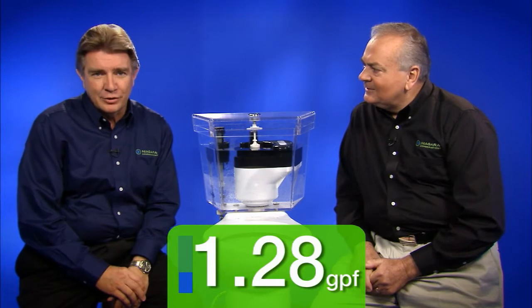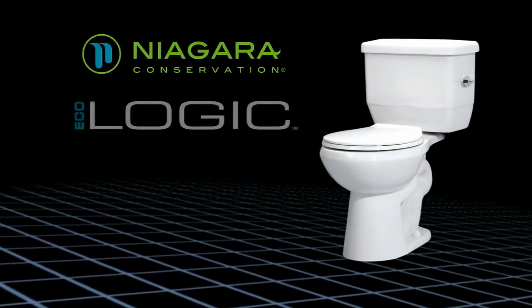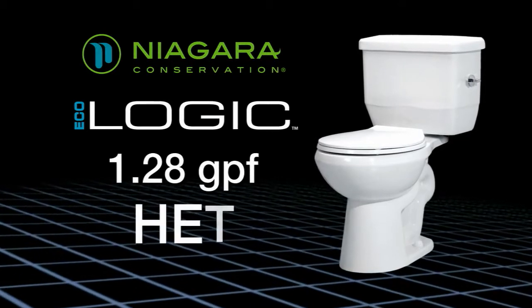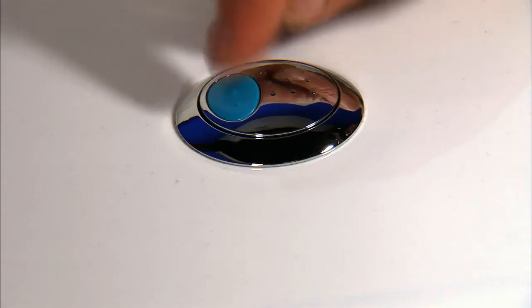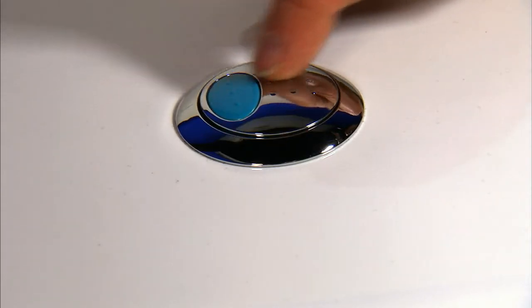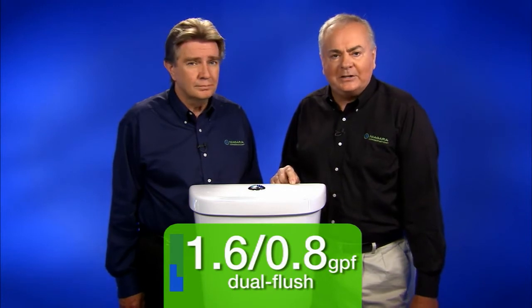And moving on, 1.28 gallons per flush, the threshold for true water conservation. A toilet like Niagara's flapperless Ecologic uses 1.28 gallons or less and is classified as an HET, a high efficiency toilet. Then you have dual flush toilets, designed to use up to 1.6 gallons to flush solid waste and as low as 0.8 gallons to flush liquids. These are marketed as tremendous water savers with average flush volumes well below standard HET.